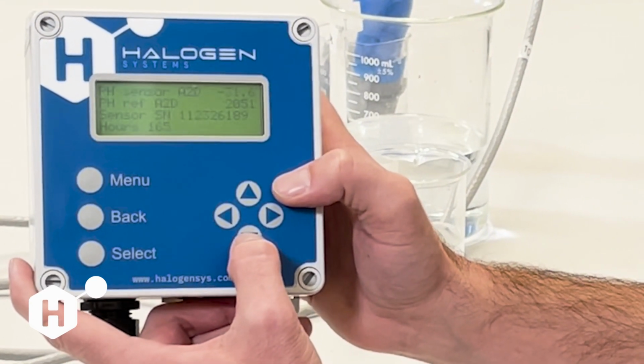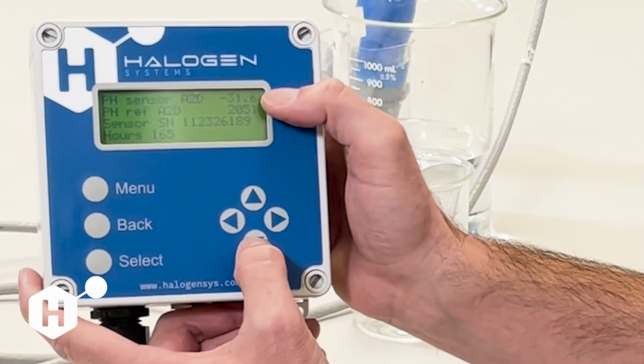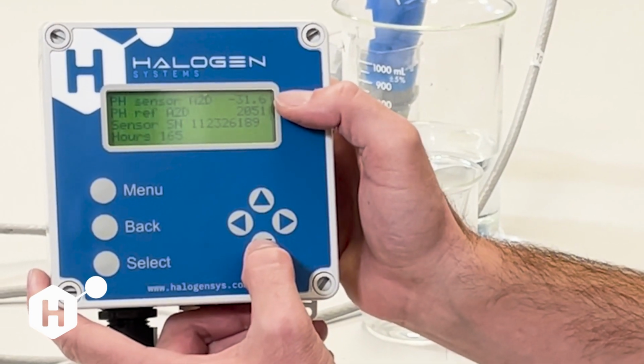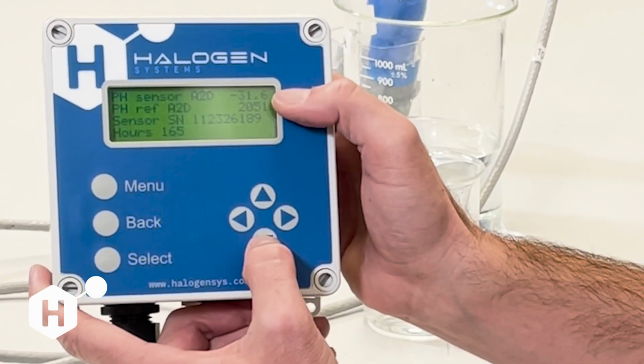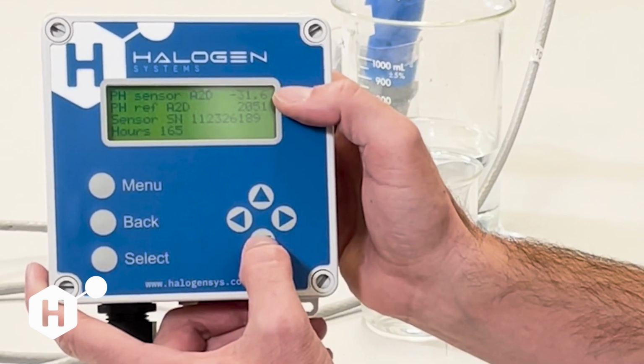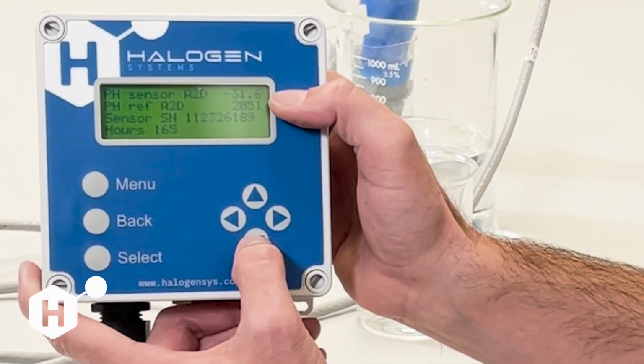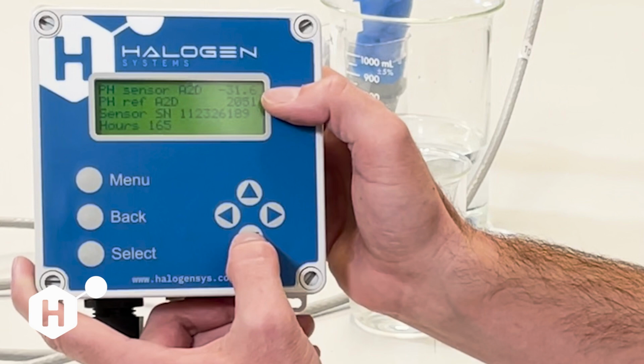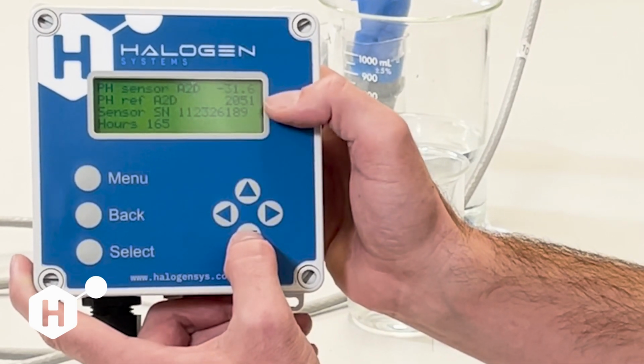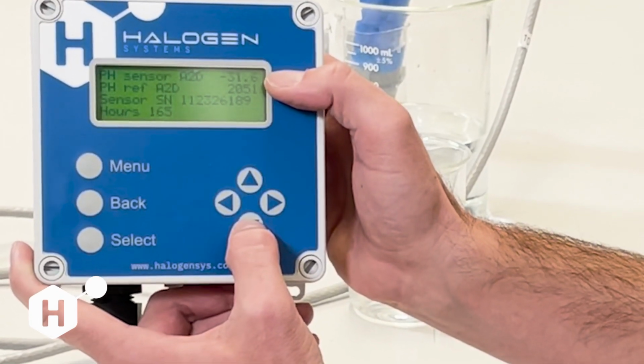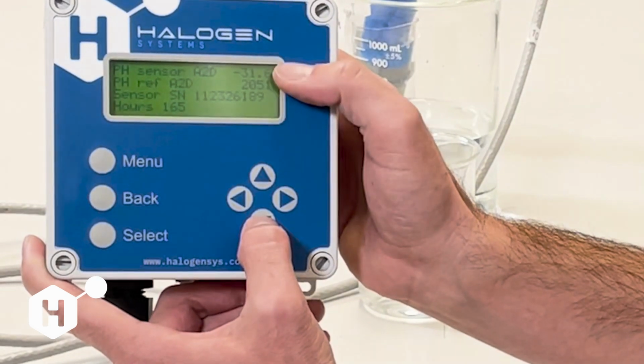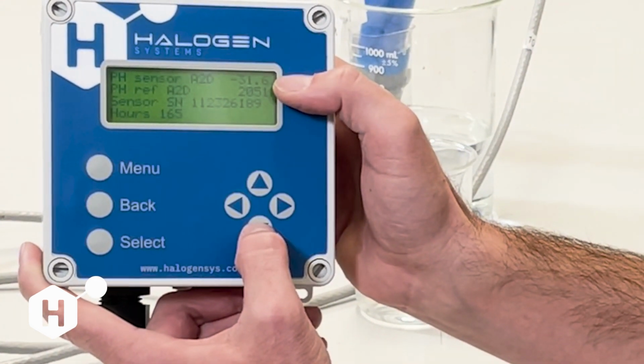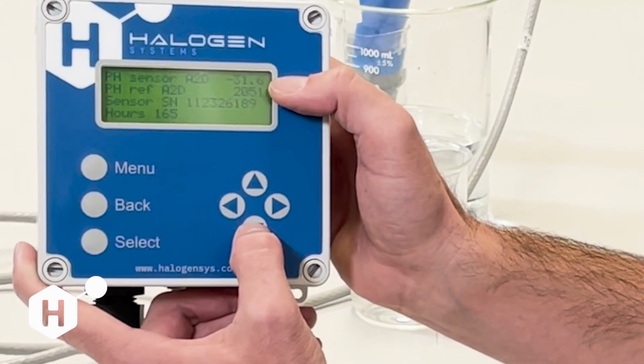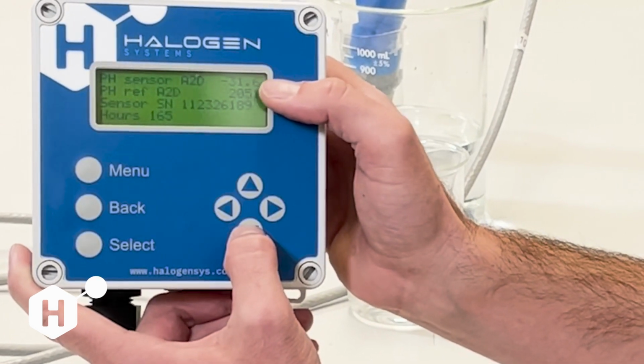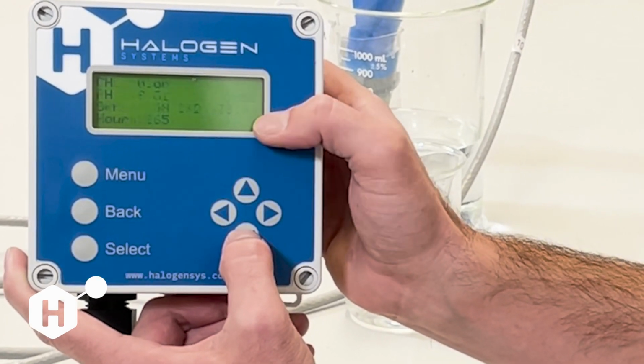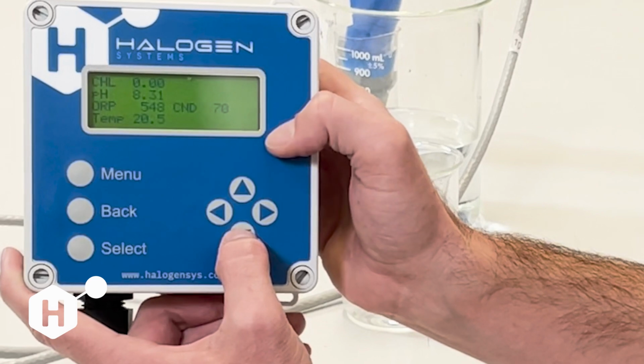The other place that we can watch to see what our pH is doing is we can come here to the pH sensor A to D and see what this value is. And we really want this value to be 0 millivolts plus or minus 40. If it's outside of that range, we're not going to be able to initiate a calibration. Ideally, this value should drop down to pretty close to 0. And I'm going to wait and watch this value for about 3 cycles. That way I know when it's no longer changing.